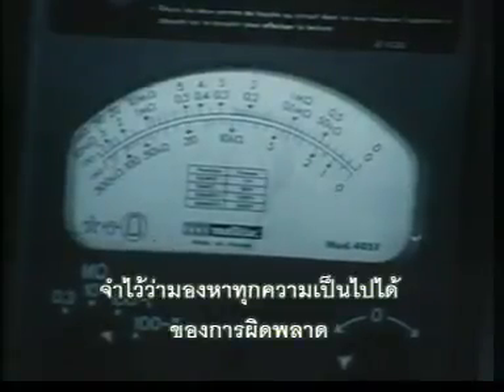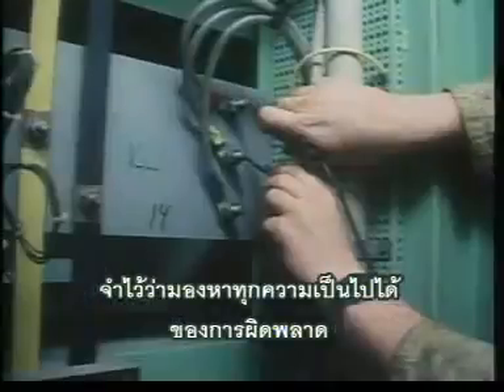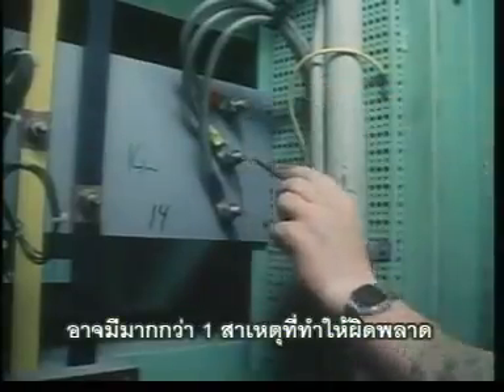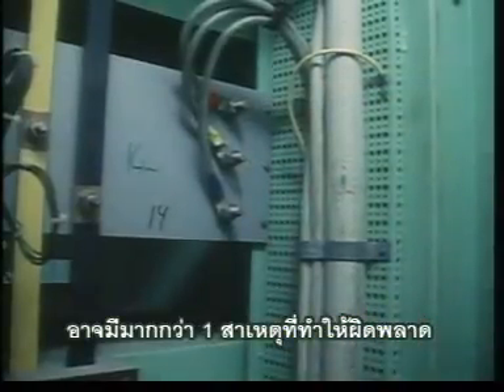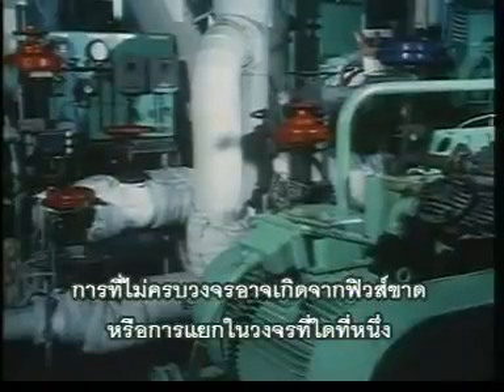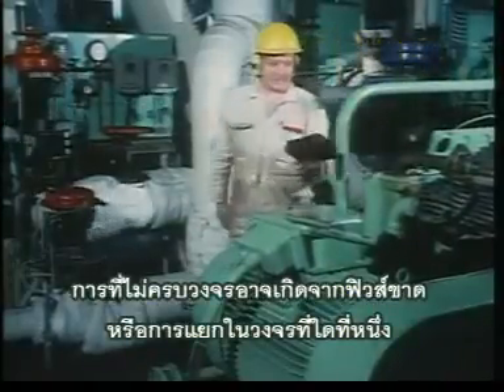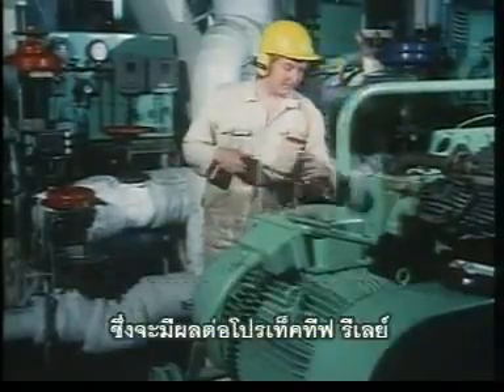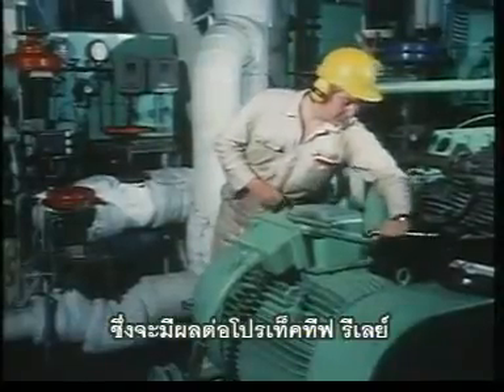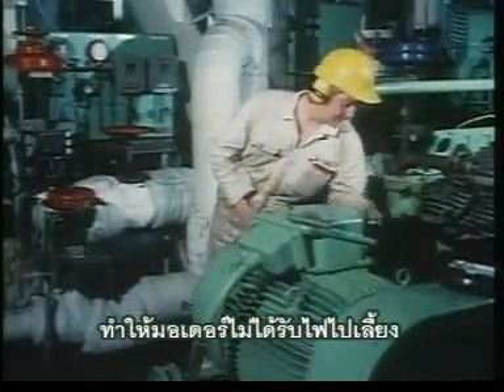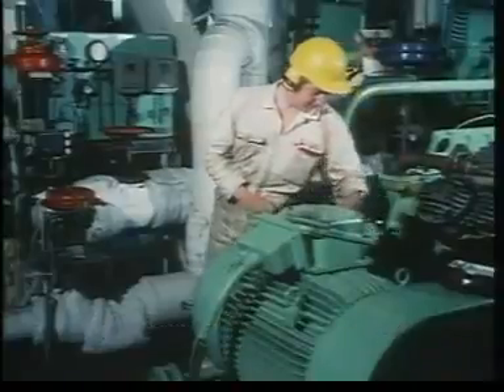Remember, you always check for all possible faults. There may be more than one causing the breakdown. The open circuit can be a blown fuse or some other break in the circuit which would have activated the protective relay, causing the motor to be cut off from the supply.